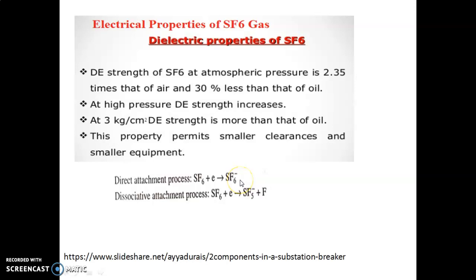When there is a fault in the system, the current-carrying contacts start separating and an arc strikes between them due to ionization of the surrounding medium. A huge number of electrons are generated due to the ionization process. When the SF6 gas molecules react with these free electrons, they form a negative immobile ion. The equation is: SF6 + e⁻ → SF6⁻.